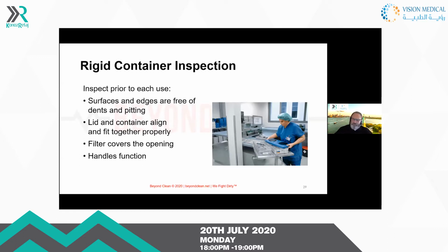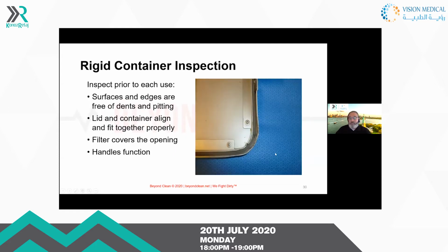And if you have to pound or work really hard to open your container, this is not the way that it should be functioning. So they should always fit. We want to make sure that the filter covers are working properly, the handles function properly. And here's a good example, again, of a set that I found while doing an inspection where the edge is certainly damaged, and then you can see the gasket is cut and damaged.